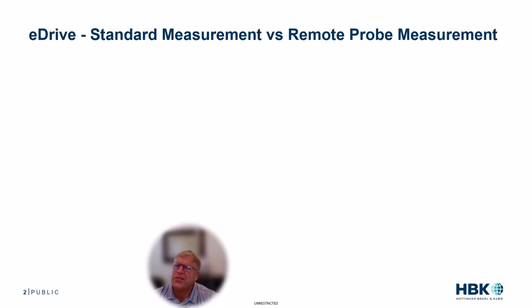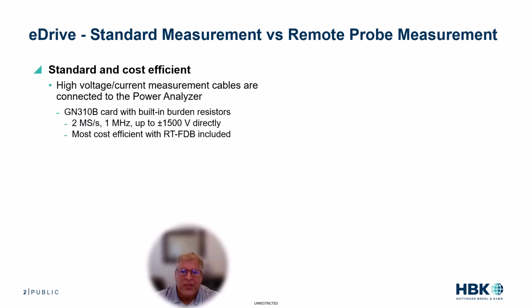Well, first, let's just do a brief overview on the why. Let's start with a comparison of the standard measurement versus the remote probe measurement for an electric drivetrain test. Now, the standard and cost-efficient method has high voltage and current copper cables running from the test point to the power analyzer using the most cost-efficient GN310B card with built-in burden resistors.